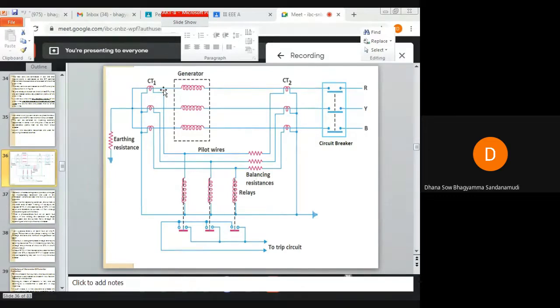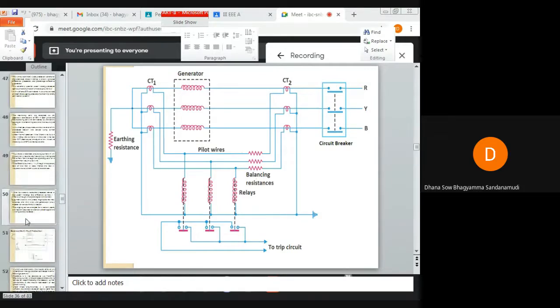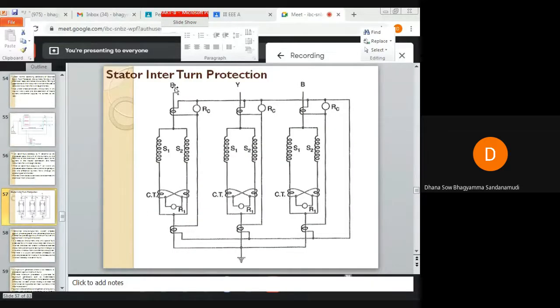Now if the current entering and leaving are the same, and if more turns are there in this winding, the algebraic sum of current will leave this winding. Even though there is a fault, you may not be able to identify it by merz-price protection, since we are measuring only the current entering and leaving. If more turns are there in this one phase, you can see the whole winding has been divided into two windings here. The current entering and leaving is measured by these two CTs, but inside, the current is dividing into two sections. So if any fault occurs within these turns, the relay must sense that fault also.